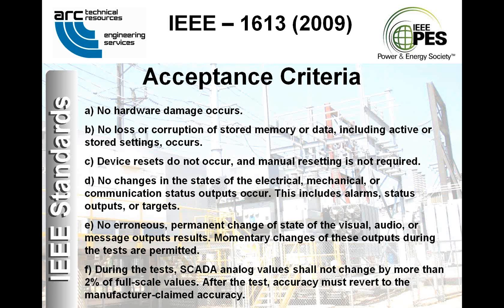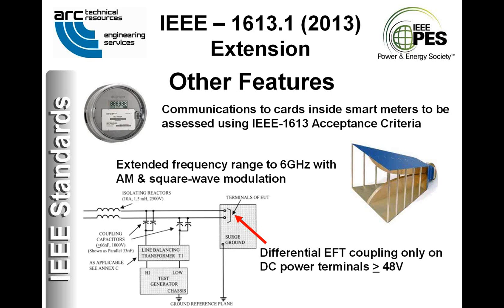Extended radiated RF immunity testing has now been mandated up to 6 gigahertz with square wave, and lower than that, 3.8, I believe, gigahertz with AM modulation. And differential EFT coupling is only run now on DC power terminals at or above 48 volts, which simulates the switched armature coil back arcing across the floating station battery terminals, so that line balancing transformer, or balun, on the fast transient generator's output shown on the lower left there is still going to be required. This was a known source of disturbances that were originally addressed in C37.90.1, 2002.